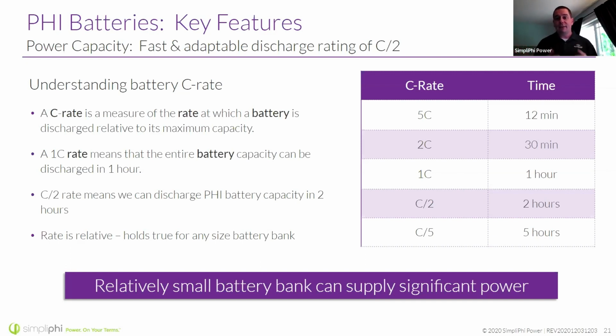What that means is that a relatively small bank can provide significant power. As we'll show in a sizing example, discharging a battery at C/2 means one of our 3.8 kilowatt hour batteries can provide 1.9 kilowatts of power. You start to stack those up, and a relatively small bank can be providing significant power.